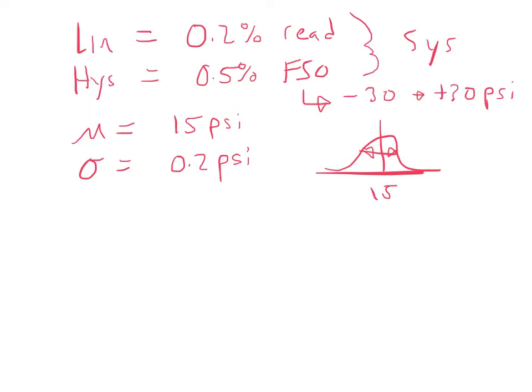So, now we have three measurements of error. We have our standard deviation, which shows our random error, and then our two systematic errors. And how we combine these is, we say, the total uncertainty of our pressure is going to be the square root of the sum of the squares of our systematic bias errors and the sum of our squares of our precision errors.